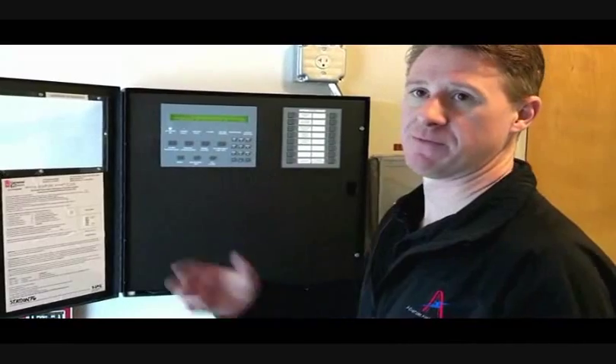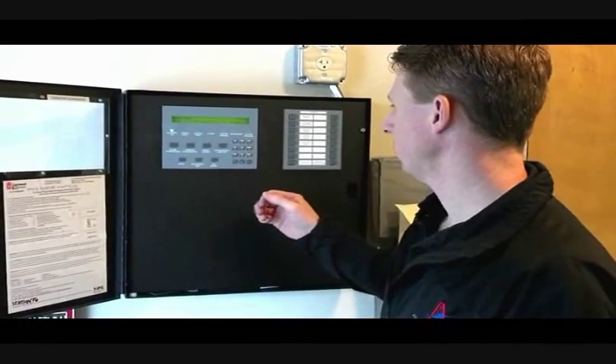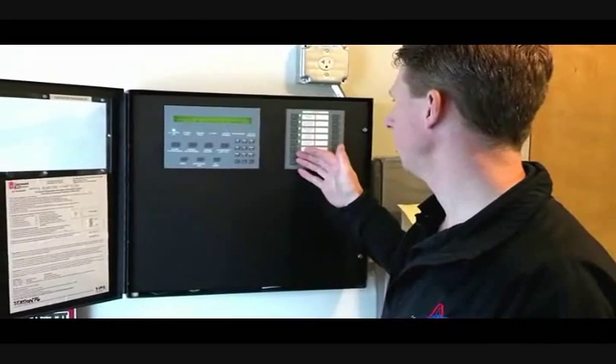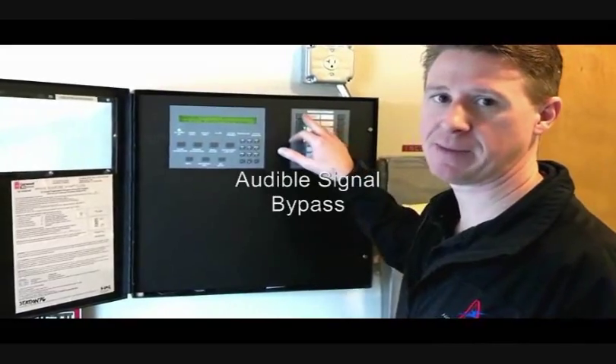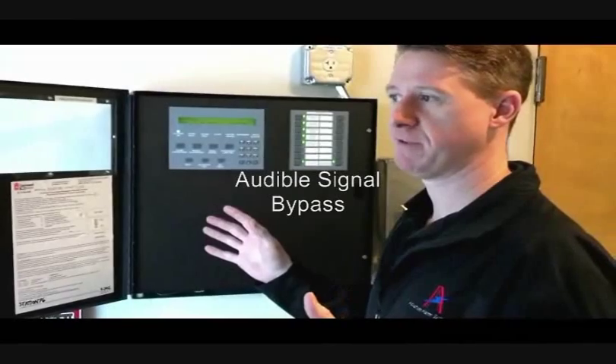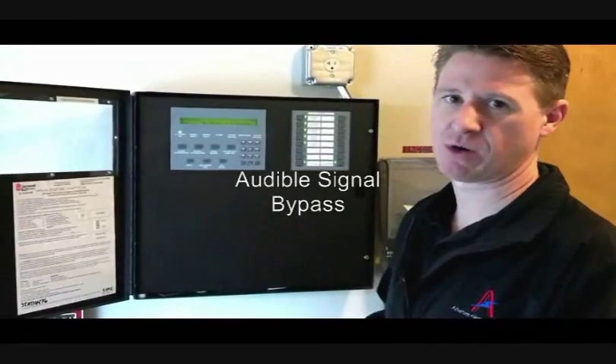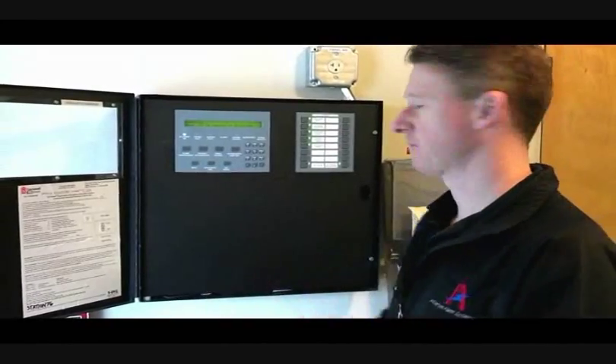It will then give you a countdown time if it's doing a system startup. We've given you a bunch of shortcut buttons on here. You've got one for your audible signal bypass — that bypasses all of the horns and strobes in the building. If you want to do a test or anything like that and you don't want to make any noise, push that and it will keep the horns from activating.